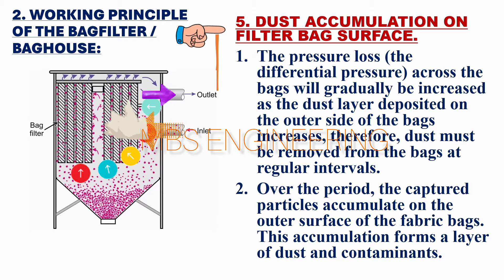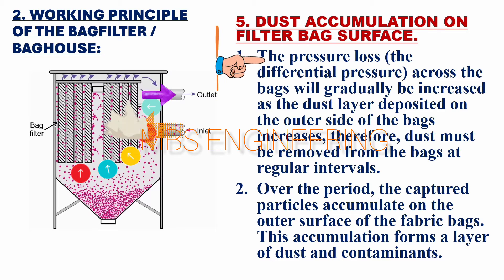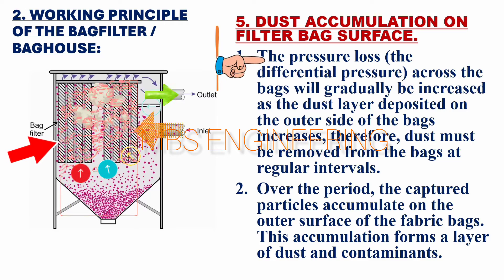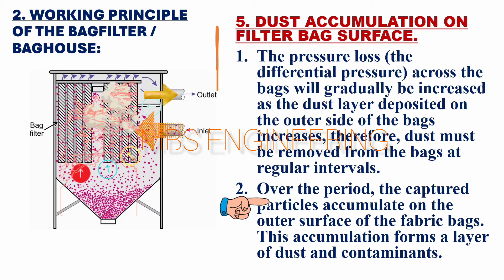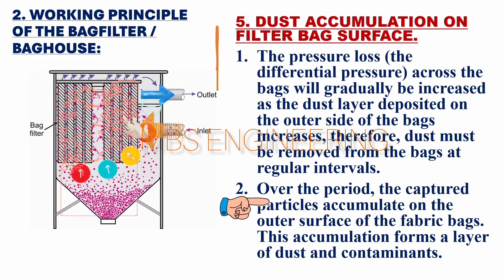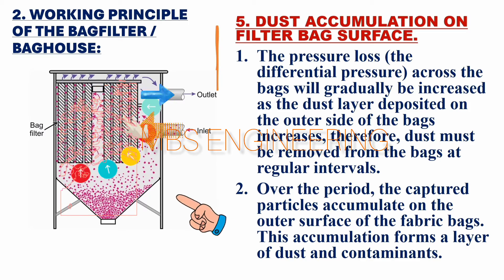Step 5 — Dust Accumulation on Filter Bag Surface: The differential pressure across the bags gradually increases as the dust layer deposited on the outer side of the bags increases; therefore, dust must be removed from the bags at regular intervals. Over time, the captured particles accumulate on the outer surface of the fabric bags, forming a layer of dust and contaminants.